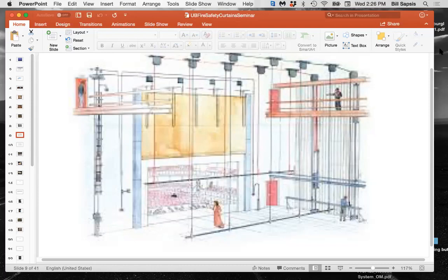They also have a mechanical release, and usually there's 6 to 9 of these doors in the ceiling. And typically what's supposed to happen is the mechanical release, as individual cables, is run down to the stage floor somewhere and gathered up and mounted on a wall, with a sign that says, in case of fire, pull these to open the smoke doors. That's what's supposed to happen.